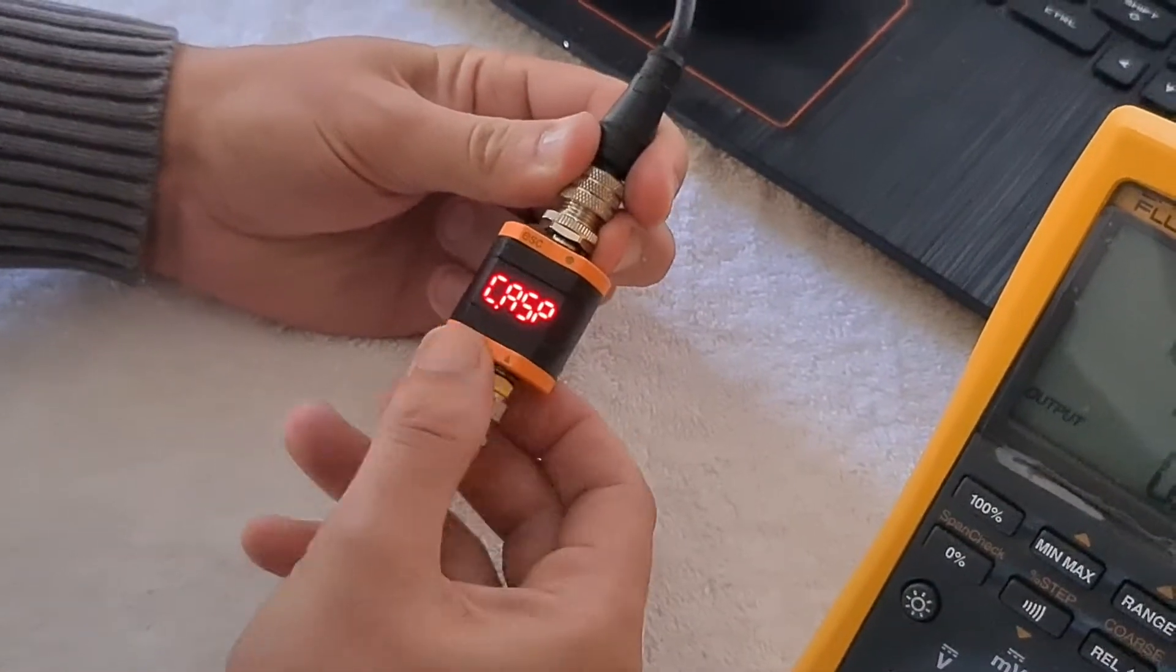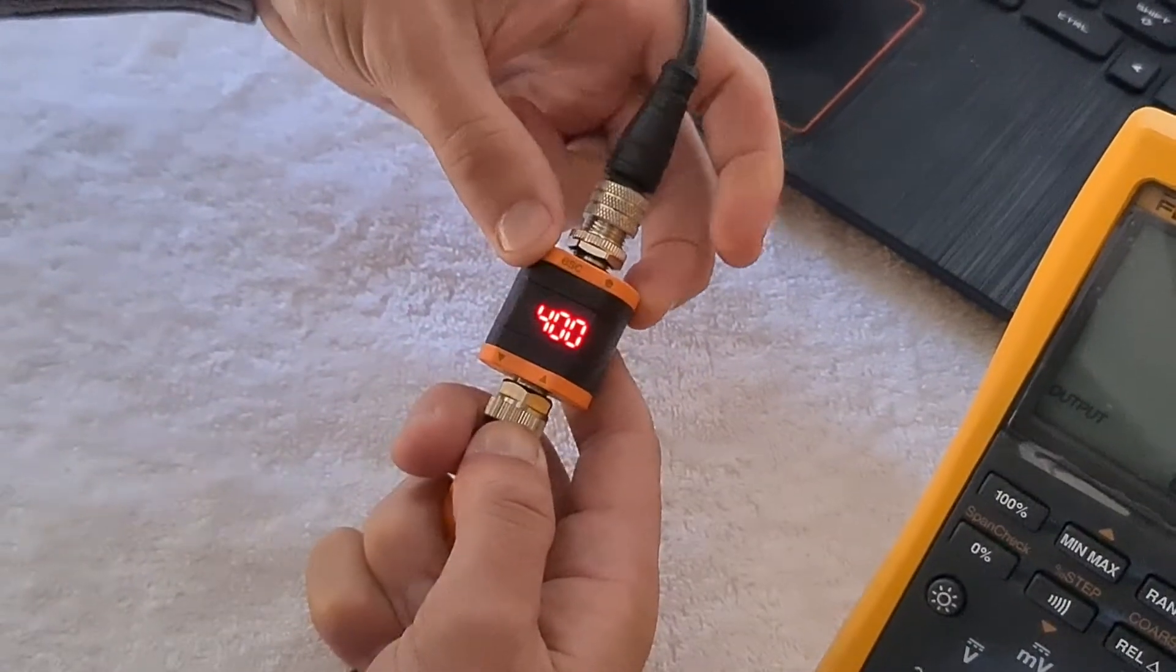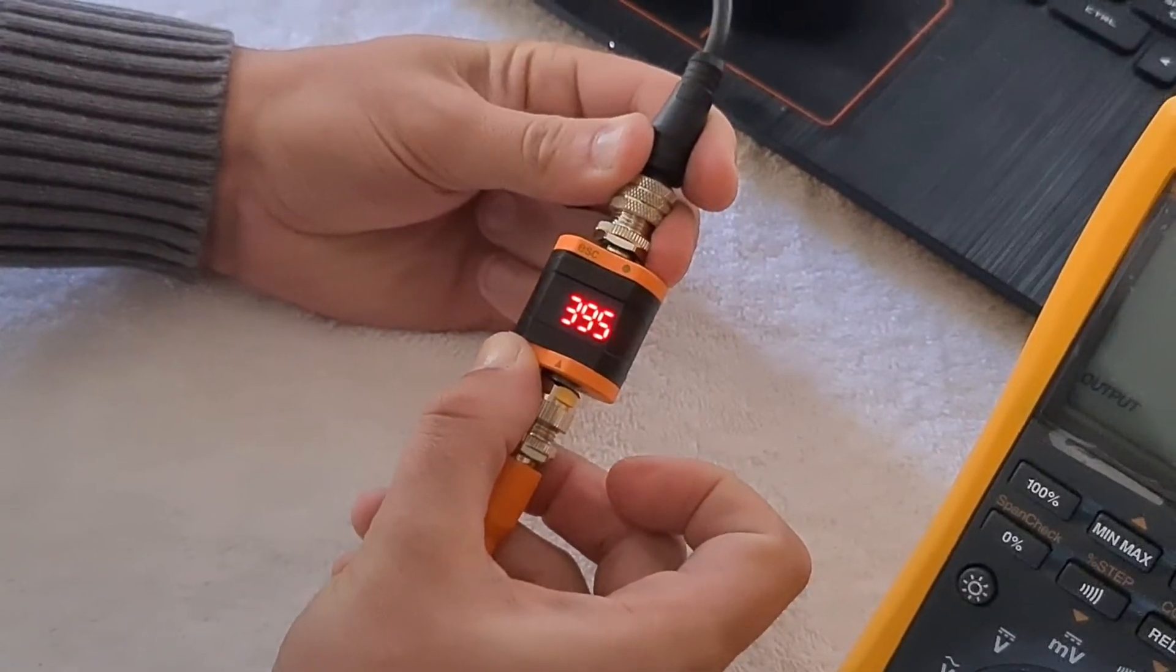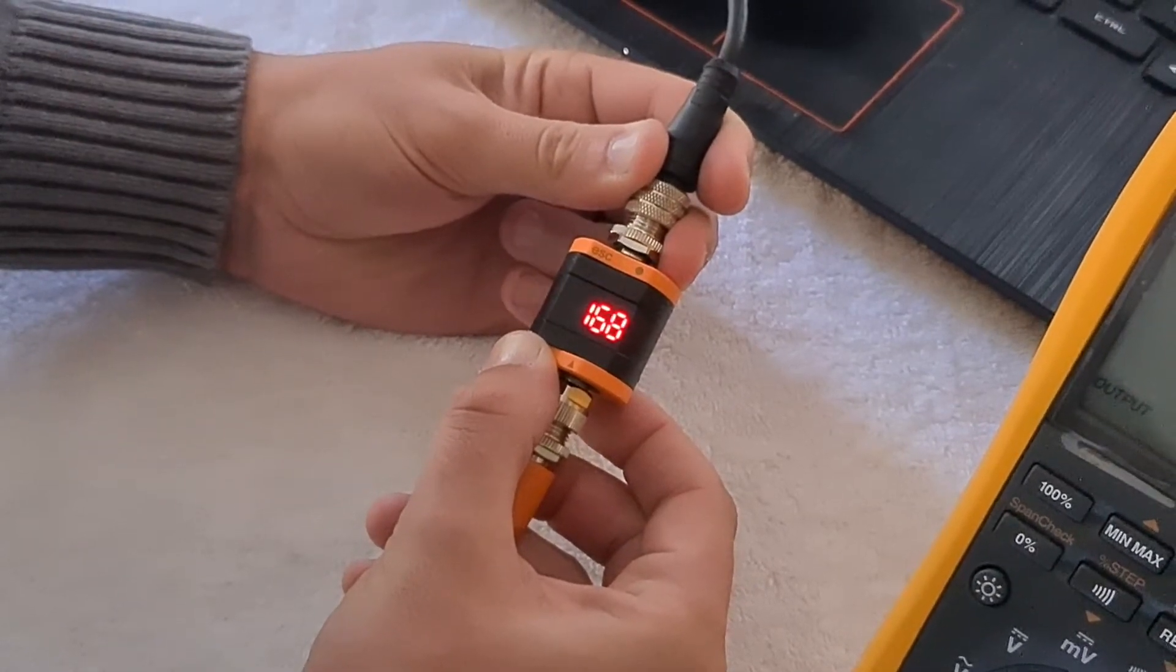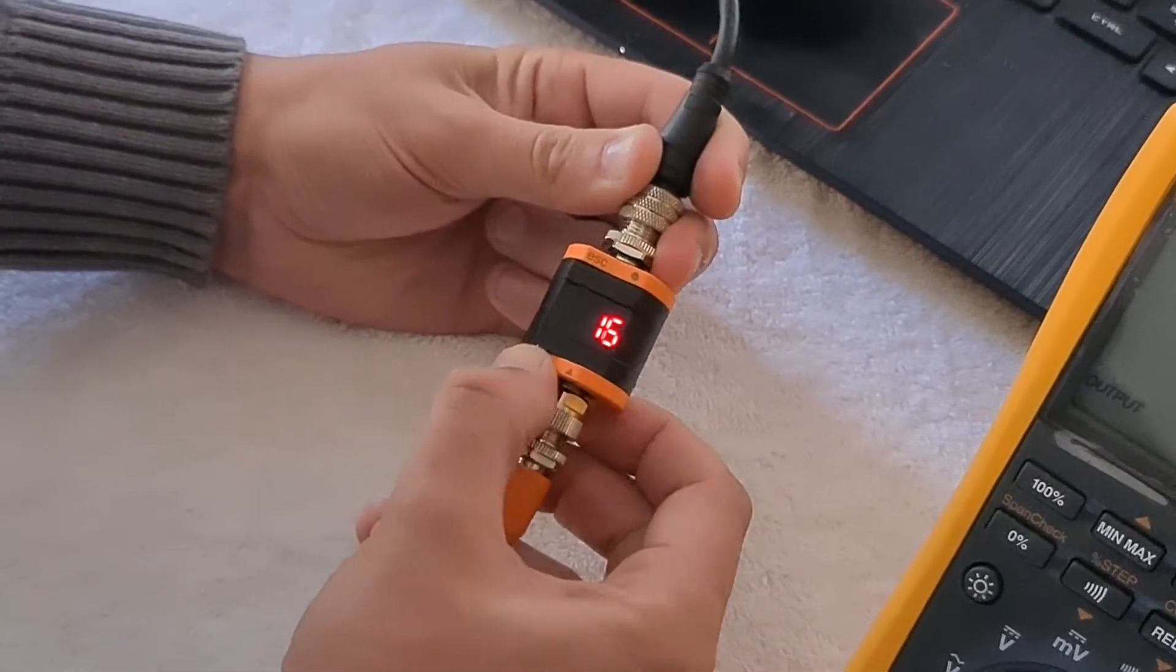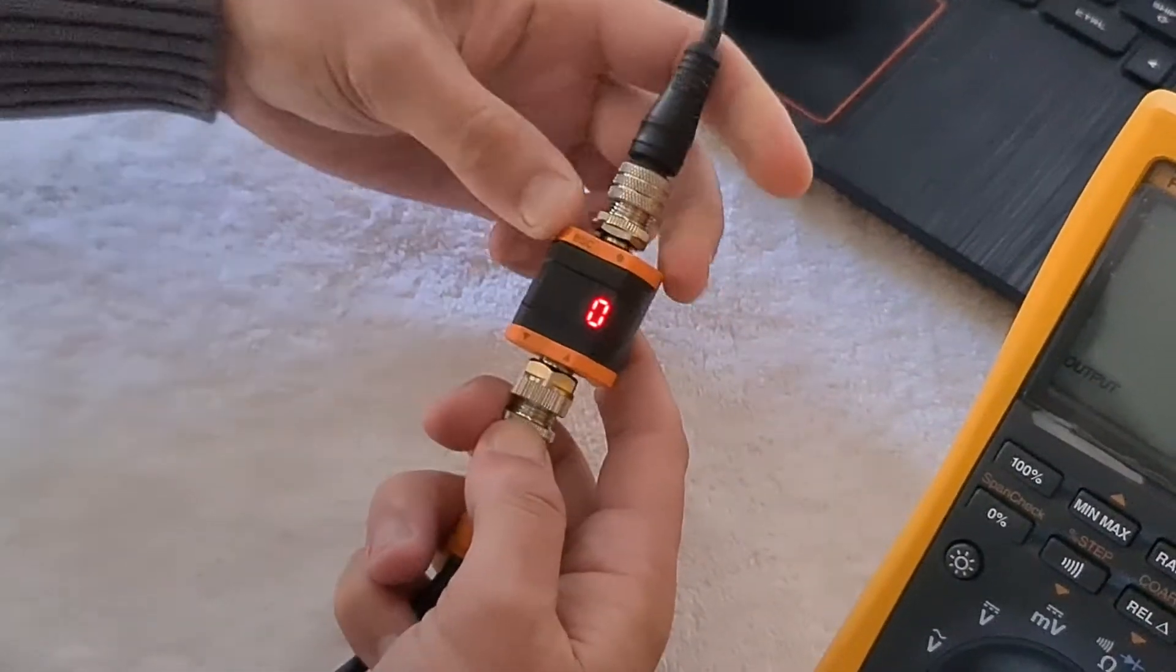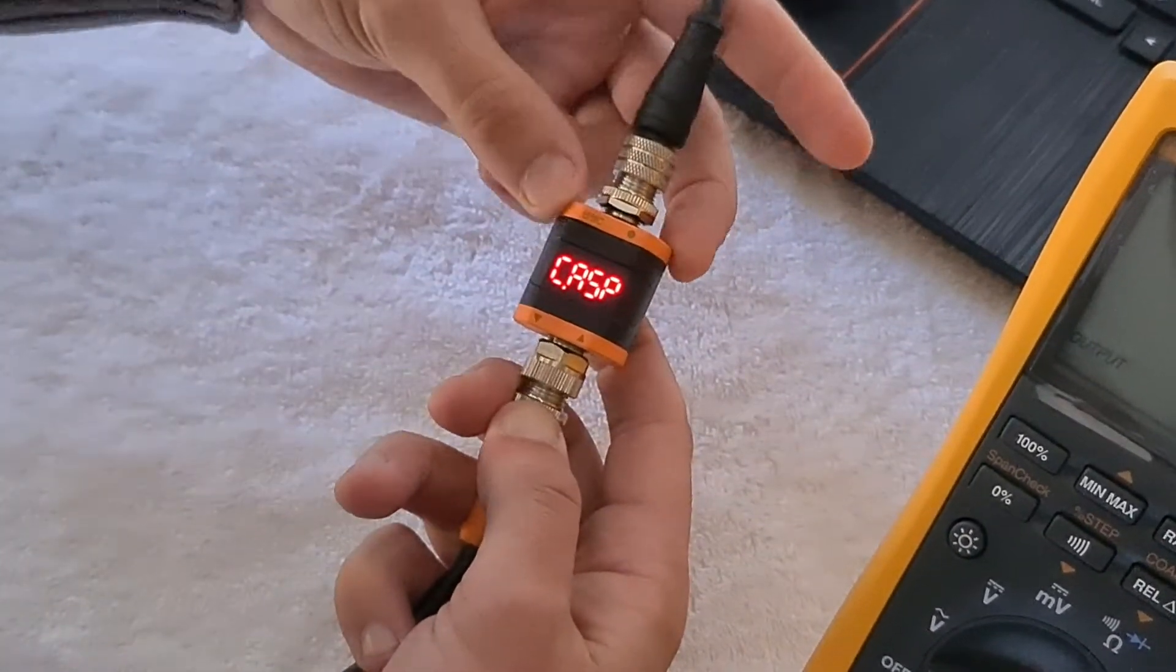Down from here, CASP, we need to change that, so enter it, top to the right. It's on 400, we're going to adjust it to zero. Holding the bottom left until it starts counting. It'll go faster, and you need to try and let go when it's close to zero. And then just do fine adjustments to get all the way to zero. Okay, we're on zero there. Top to the right to save it. And you can go in again, top to the right, it's been saved at zero.